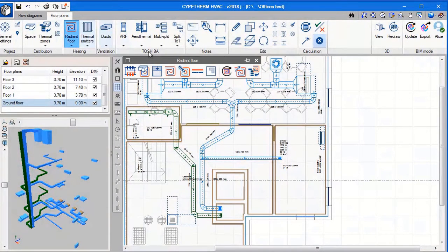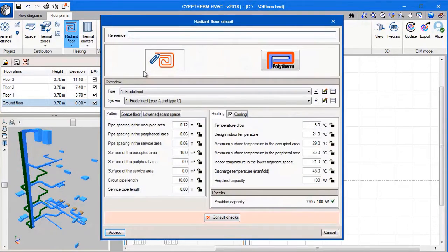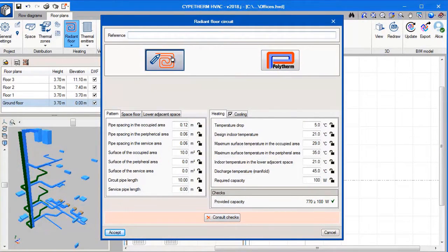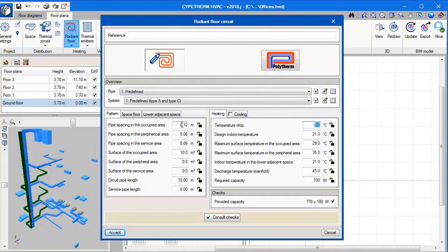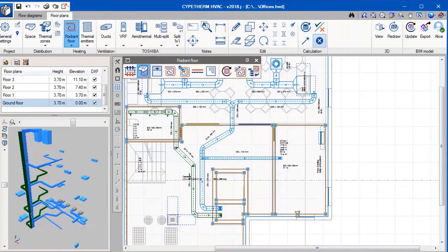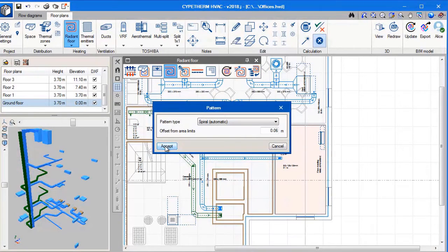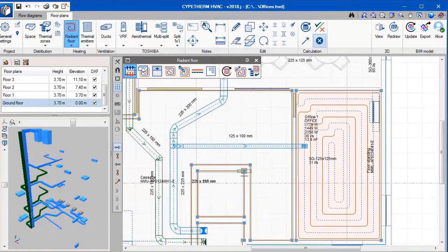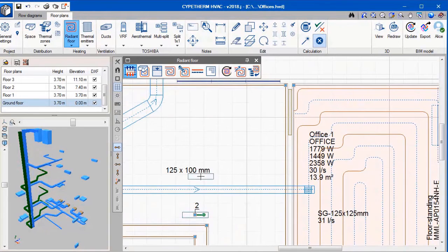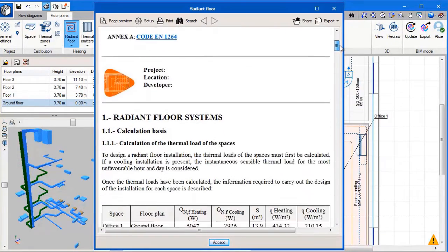We are now going to add a radiant floor. To add a radiant floor, all we need to do is select the design conditions. We uncheck the cooling box because we only want the heated radiant floor. Once we have selected the design conditions, all we need to do is highlight the area which we wish to add the radiant floor to, and press the radiant floor button and choose the pattern type. We also need to choose a manifold for the radiant floor, and we then select pipes to connect the manifold to the radiant floor. We can view the report for the radiant floor and all the calculation information.